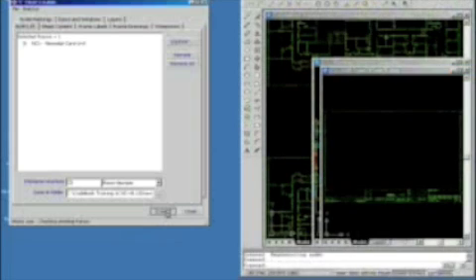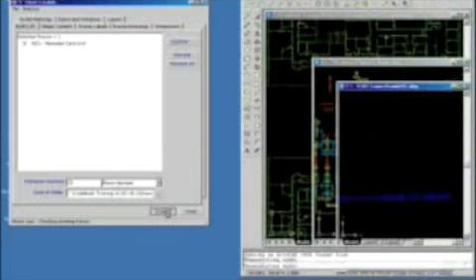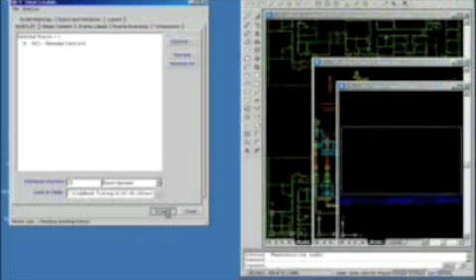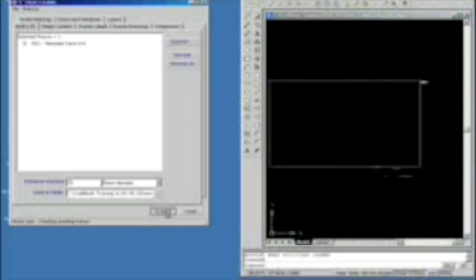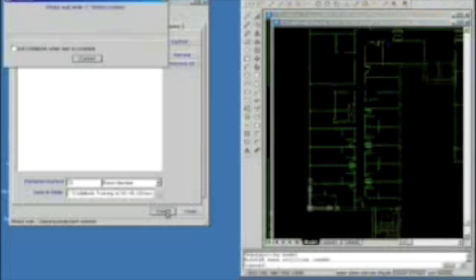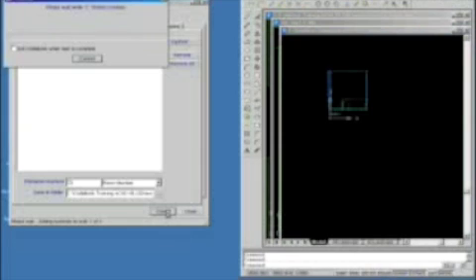CodeBook will then drive the CAD engine, in this case AutoCAD, to create a brand new DWG, locate the room, draw the elevations of that room, locate the equipment at the correct fix heights on those elevations, clip Xref the plan of that room to the centre of those elevations, wrap a title sheet around it, fill the title sheet in with some pertinent information from the database, drop it into paper space and file it away and move on to the next one.